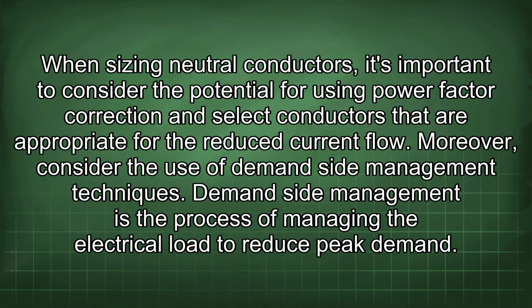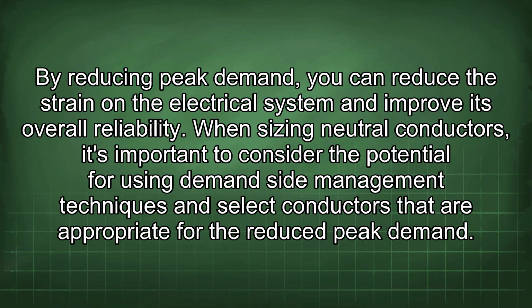Moreover, consider the use of demand-side management techniques. Demand-side management is the process of managing the electrical load to reduce peak demand. By reducing peak demand, you can reduce the strain on the electrical system and improve its overall reliability. When sizing neutral conductors, it's important to consider the potential for using demand-side management techniques and select conductors that are appropriate for the reduced peak demand.